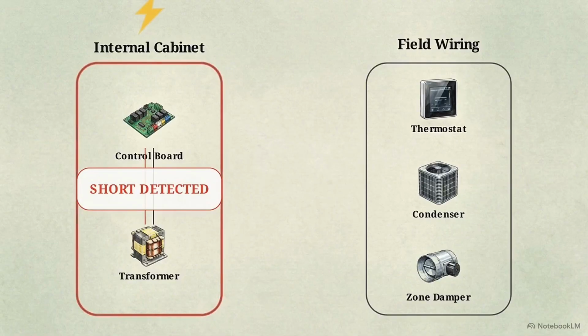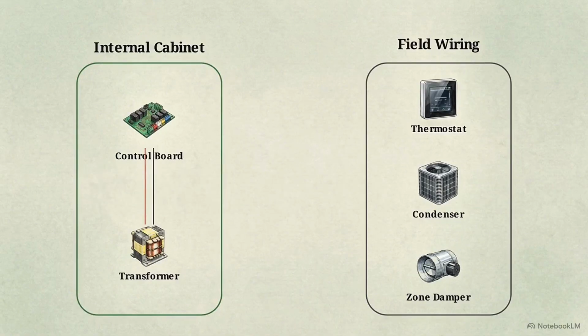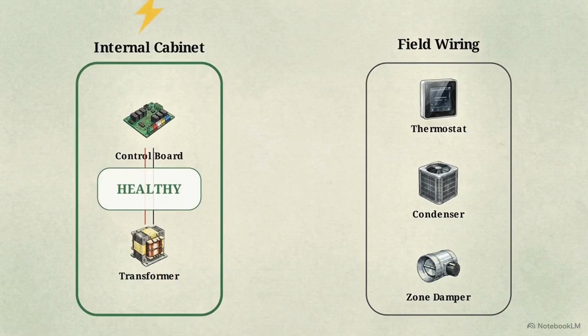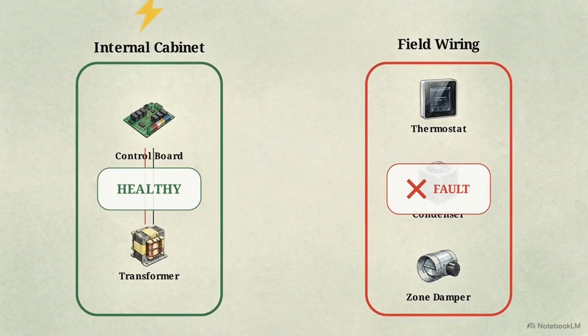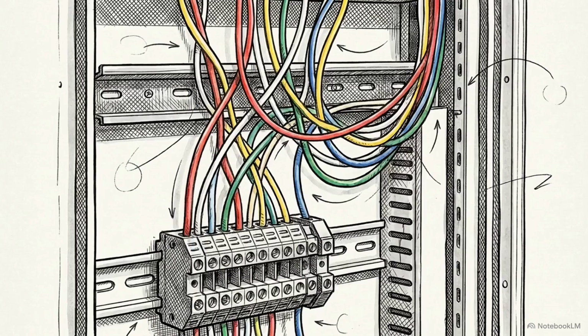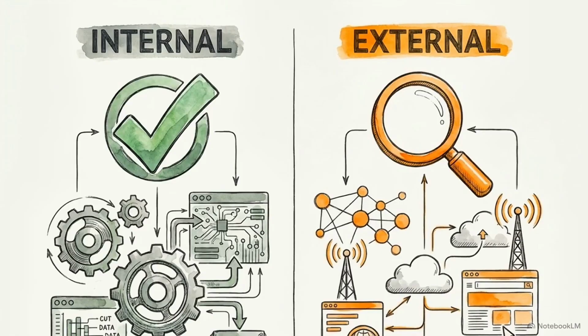As we see in this diagram, if the board registers a short or the resettable breaker trips immediately, the fault is inside the cabinet. If the board operates normally and the breaker holds, as the diagram shifts to show here, the internal components are healthy. The short is sitting somewhere in the field wiring. We have now proven that the issue lives on the external side of the system. Disconnecting the external loads cuts the diagnostic field in half. You now know exactly which side of the terminal block requires your attention.